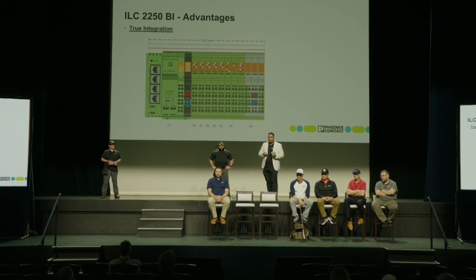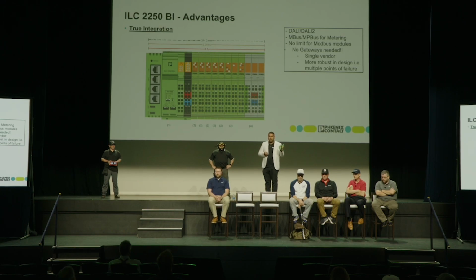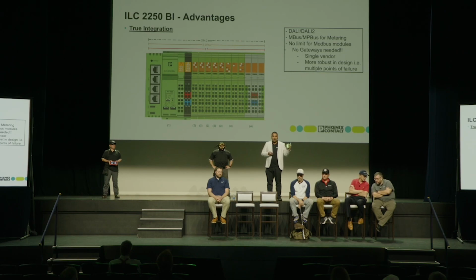True integration — what do we mean by that? True scalability. Dali and Dali 2, for example, we do native modules that connect directly onto the bus itself, so you don't need any gateway, no IP gateway or anything else to convert that protocol into another controller. It's native inside our ILC 2050 controller. It's a single vendor as well, not having to use a different vendor — it's still Phoenix Contact. It's more robust in your application and design, meaning there are no multiple points of failure in your design either.